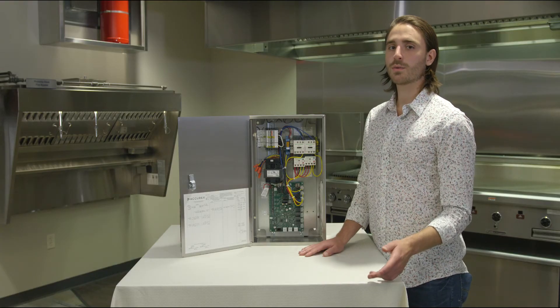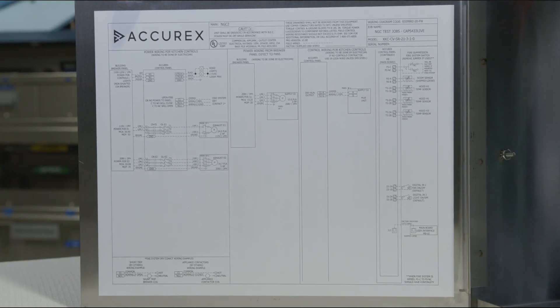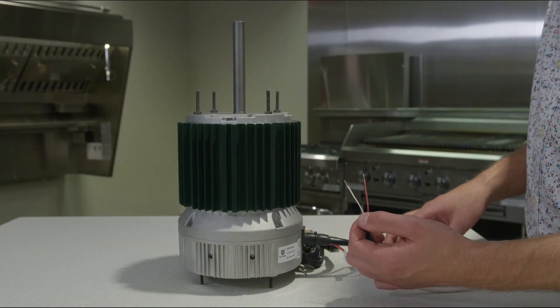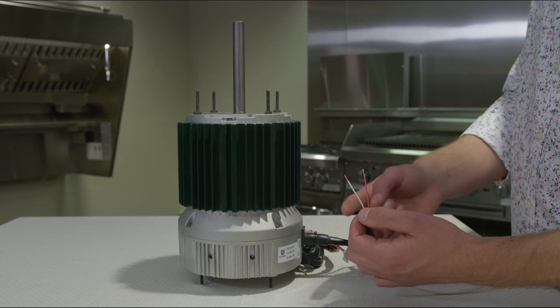Next, we'll move to the control wiring. This wiring is to be done by a controls contractor or electrician, typically using 18 to 22 gauge wire and remembering to follow all applicable codes and industry standards. While fans equipped with motor starters and VFDs typically don't require any additional control wiring, Greenheck Vari-Green motor equipped fans require a simple two wire connection. For Vari-Green exhaust fans, there will be terminals labeled E for exhaust with up to eight terminals. These terminals contain an S plus and S minus connection. Wire each pair of terminals to the corresponding Vari-Green motor, connecting the S plus terminal to the red wire and the S minus terminal to the white wire on the Vari-Green motor.